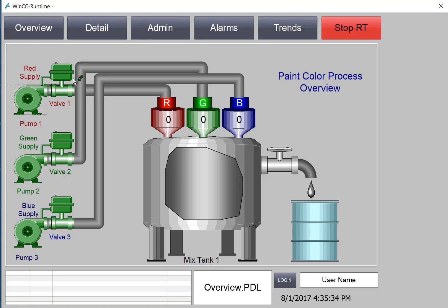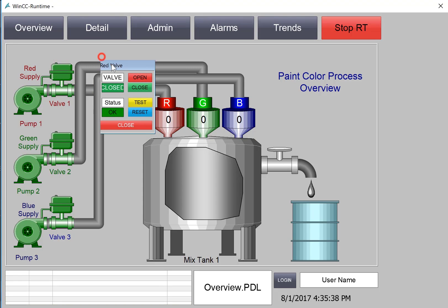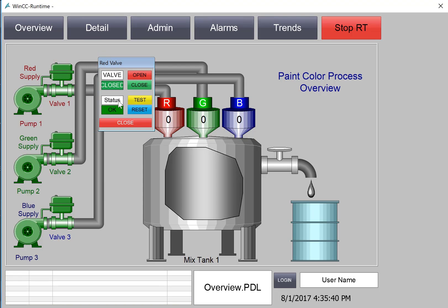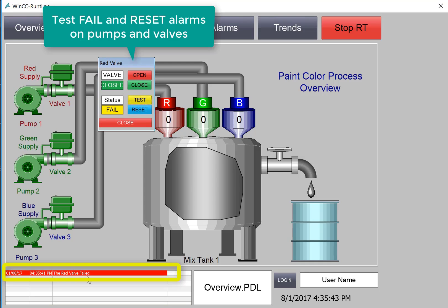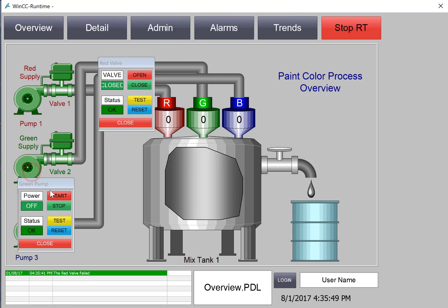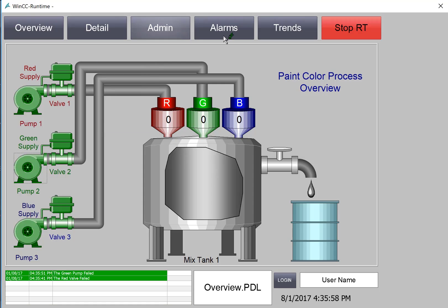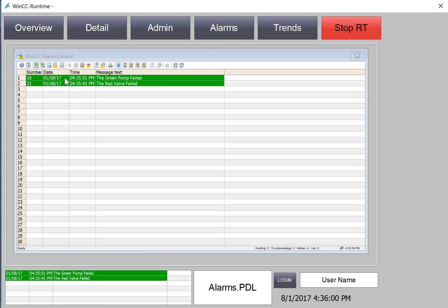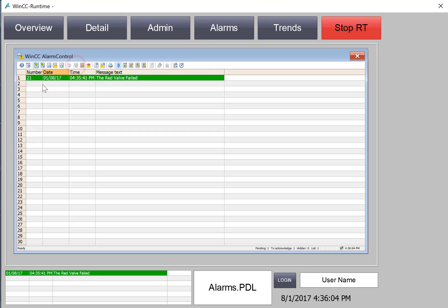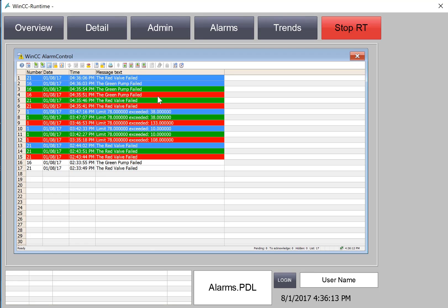In Runtime, we can test our pump and valve fail alarms by using our pop-up controls. So on Valve 1, I'll hit Test. And you can see we get our alarm here. I'll reset. And it turns green. We'll test one of the pumps. And there's our green pump fail and our reset. If we go to our alarm screen, we can select these and acknowledge them. They leave our active display. We can go back to the long-term archive list and see a list of alarm activations so we have a complete history of when the alarms come in and go out. We can tell the states of the alarms by the colors.